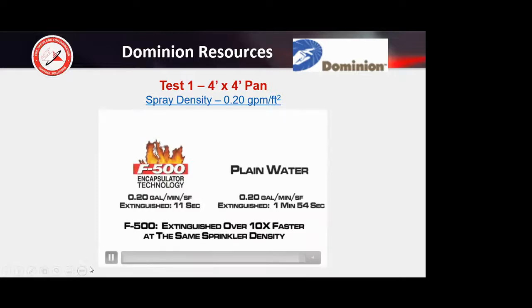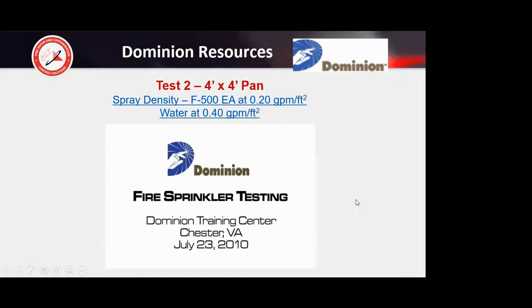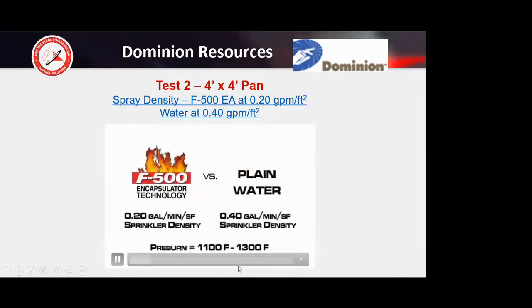So the conclusion was that we extinguished over 10 times faster than the plain water at the same sprinkler density. They ran the test at 0.15. The F500 put the fire out in 30 seconds, and the plain water could not put the fire out. That's why we're showing you the 0.2, because the plain water couldn't put the fire out. And then here, this is to show the 0.2 for F500 versus the 0.4, which is the FM Global recommendation.